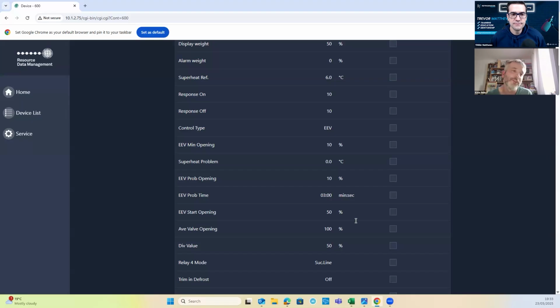And that's useful if you've got a brief issue with the rack that you've solved, and then the case will get away by itself. If you've got an iced up coil, you don't necessarily want a problem opening of 10% because you're going to keep feeding that coil 10% refrigerant all the time. You might want it to say, no, I've got low superheat, I'm going to stop. Right? So it depends on your setup.